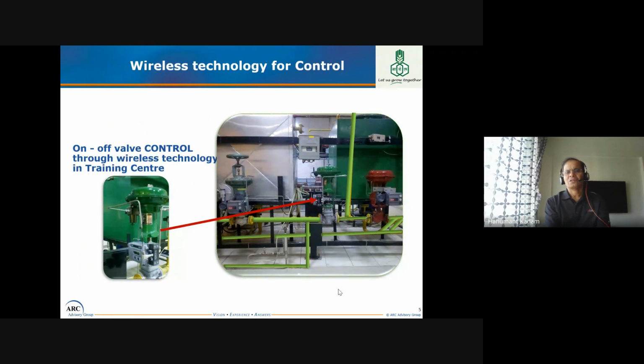So in this picture, you can see a wireless control valve, on-off type. Initially, the technology was developed in the wireless positioner for on-off, and now it is available for the analog type. Means you can have a 0 to 100% open-close type of positioner in the wireless category. So you see this valve is a wireless valve from Fisher. This valve with this positioner is a wireless positioner, and at present it is on-off, and this is a normal control valve you can see with a foundation fieldbus positioner here. Sorry, this is a foundation fieldbus positioner, and this is a normal pneumatic positioner.